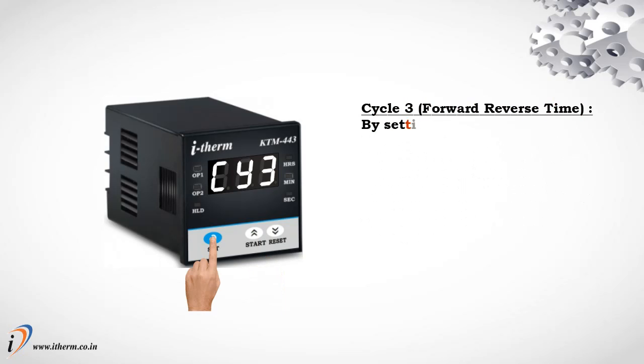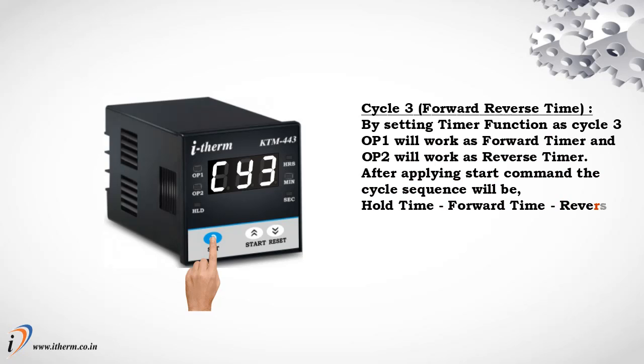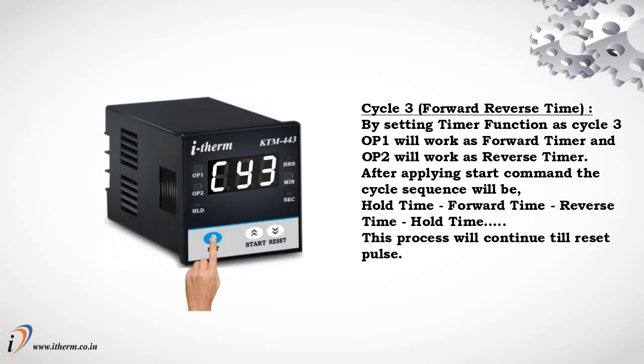Cycle 3, forward reverse time: by setting timer function as cycle 3, output 1 will work as forward timer and output 2 will work as reverse timer. After applying start command, the cycle sequence will be: hold time, forward time, reverse time, hold time. This process will continue till reset pulse.